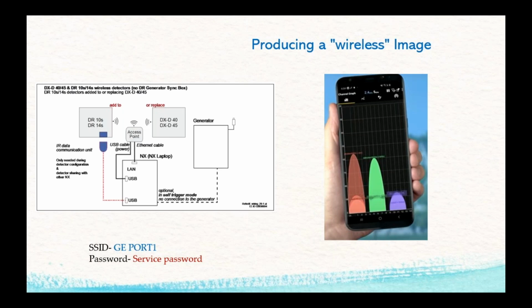When we go in to install one of these, you need what I call just a sniffer, an app on your phone or your laptop that can monitor all the radio frequencies in the room, either at 2.4 or 5 gig. What we normally do is carry this around the whole room, down the hallway, anywhere where this portable is going to be, and we look for the highest amount of signal with the least amount of crosstalk. If you have these high peaks and they're narrow, that is an ideal situation. If you have lower peaks that span across the other signals, that's crosstalk and that's interference. So that image is not going to come across as cleanly as we need it to.